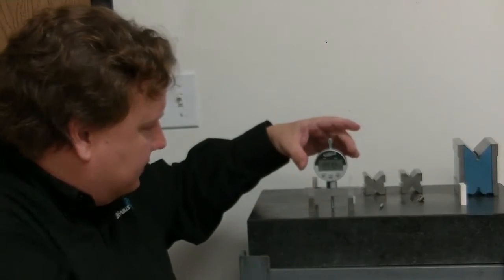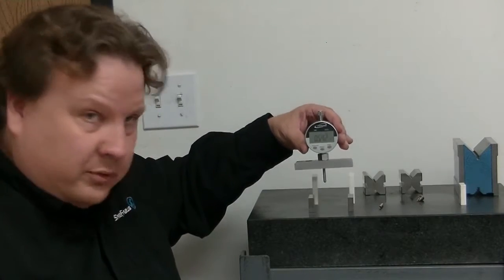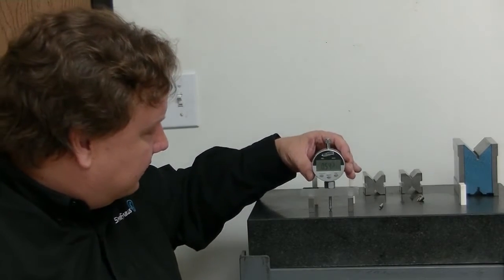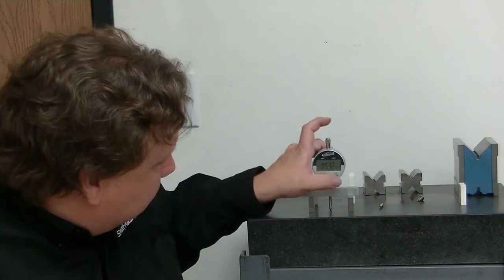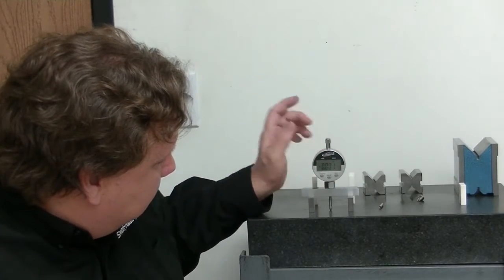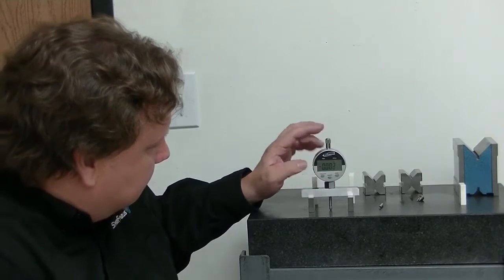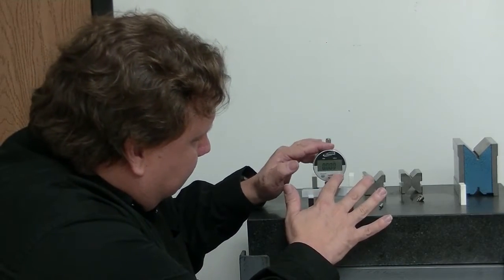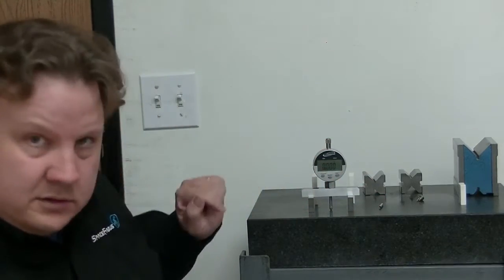So I have these two one-inch calibration blocks and I'm going to set it on there to calibrate it and I'm going to zero it out by pushing zero. Okay, so now I've got to hold it still when I push zero. So now I've got it zeroed out.